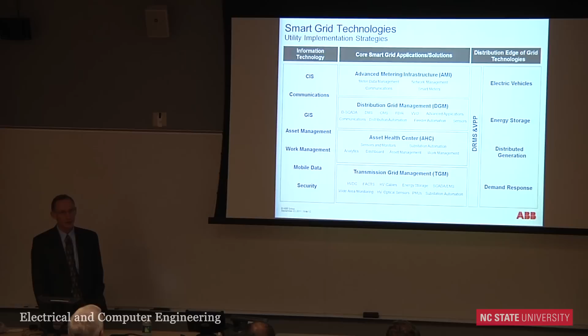What I mean by that is using smart meters to provide outage notification and service restoration verification, combining the AMI meter information with distribution grid management. Tying distribution grid management and outage restoration with work management and mobile data. Using demand response as a tool to help restore parts of a system that may be de-energized, where once you've isolated faults on a hot summer day near peak load, lowering demand on those feeders with a demand response program gives you more flexibility to reconnect customers.